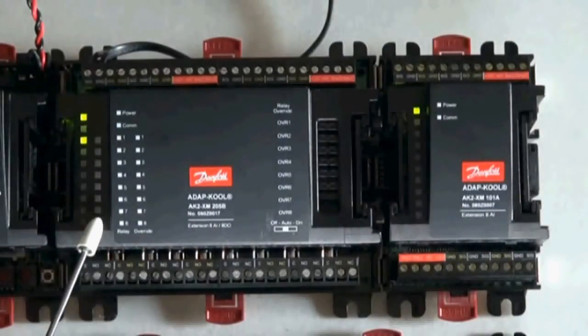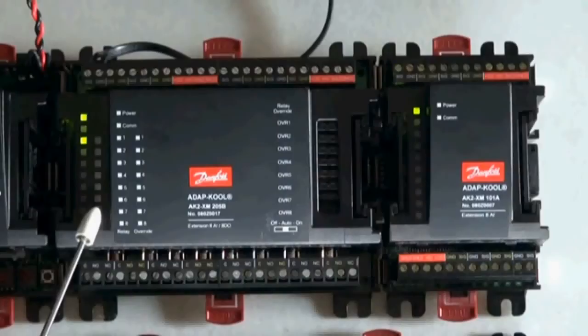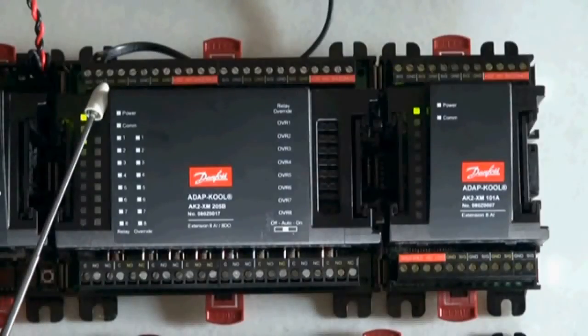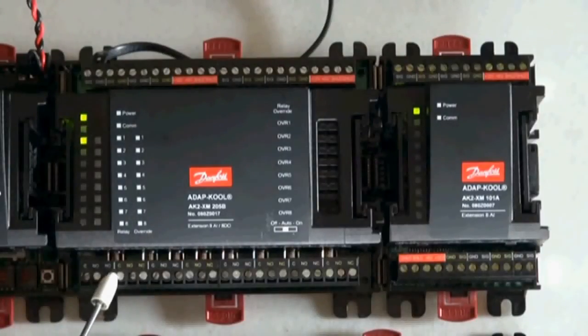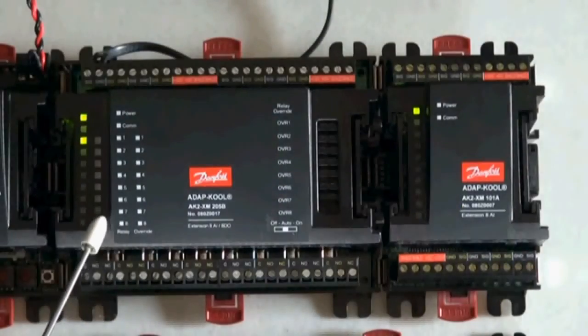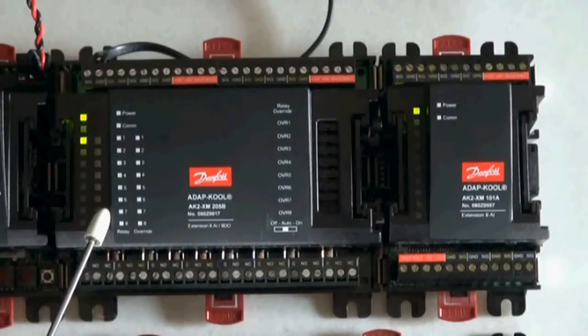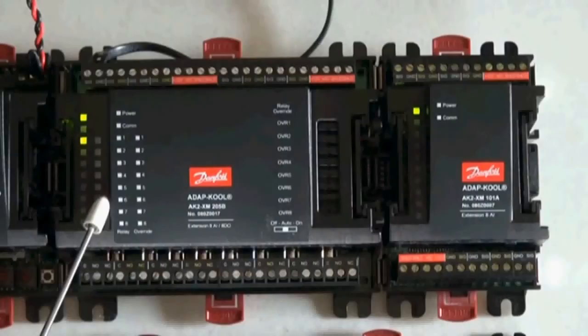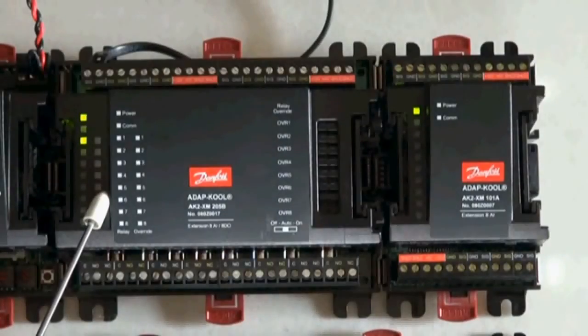This module is usually known as the combo module. It contains 8 analog inputs or 8 dry contact digital inputs at the top and 8 relay connections at the bottom. This is what's considered a full-size module. There are 3 modules that are full-size: this combo module, another module which is relay only, and the stepper module.